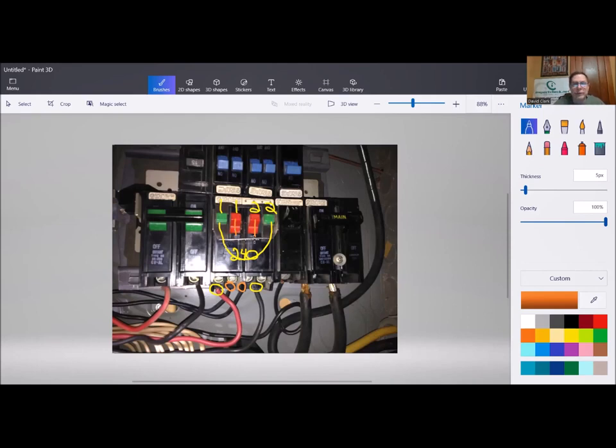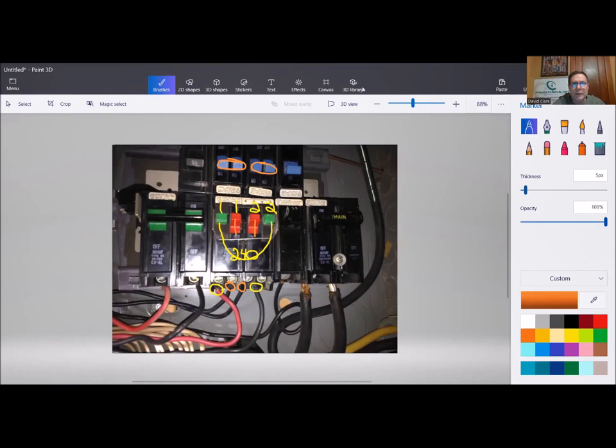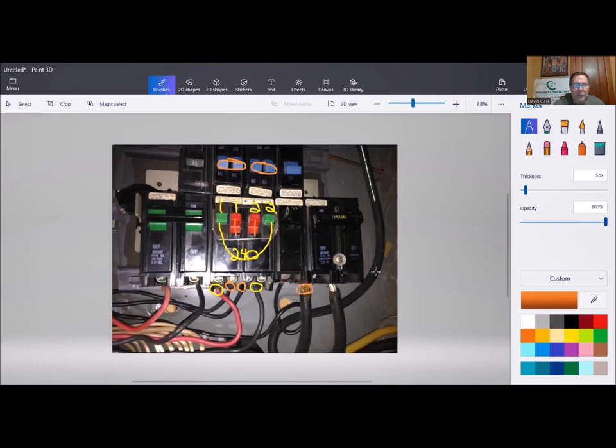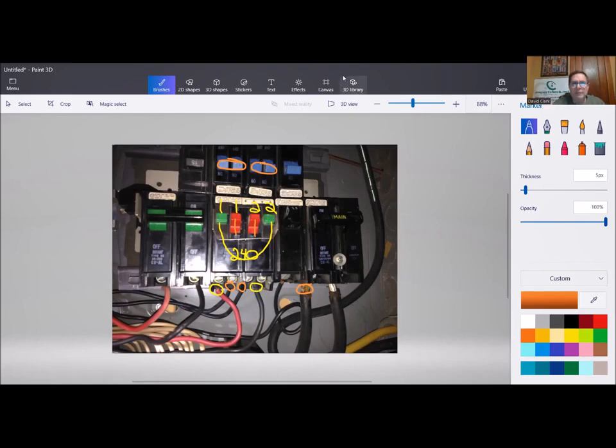So you would use that if you ran out of room. And you can see that they did it up here. They put a couple of minis and a couple of minis. So maybe more than what we want. So we're going to take a look at a newer one. So I would recommend in this case, because I don't know, more than likely, we've got some corrosion here in the panel. It's definitely an older main service panel. When I start seeing minis, I think maybe they just need more service. We would take a look at the house and see if they need more service, which it sure looks like they could probably use. That looks like 200 amp service coming in. But when I start seeing minis and things like this, I recommend they get a bigger panel and maybe bump that service up.